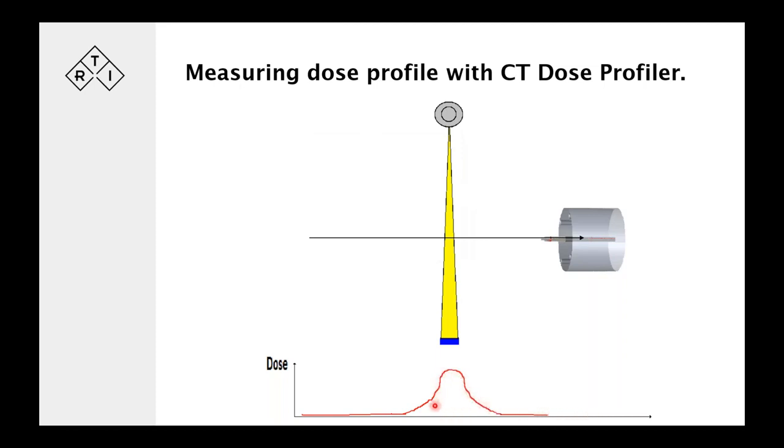So what we actually see here, thanks to the sampled dose values, is that we can integrate the whole area below the curve, and that will then be the CTDI value as defined in the standard CTDI. And it's from -infinity to +infinity, since we capture everything, all the dose tails.